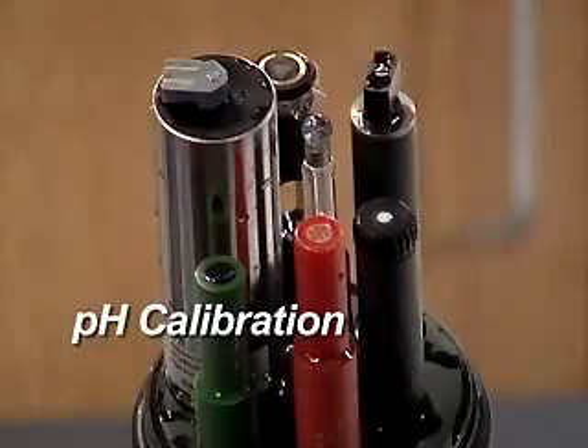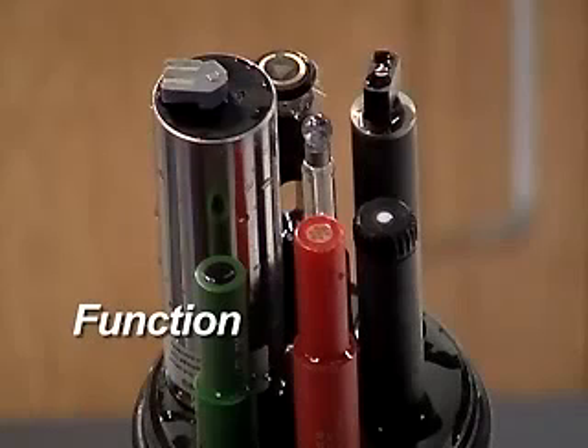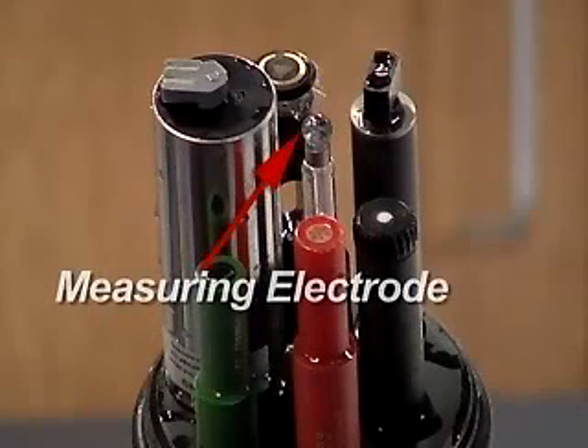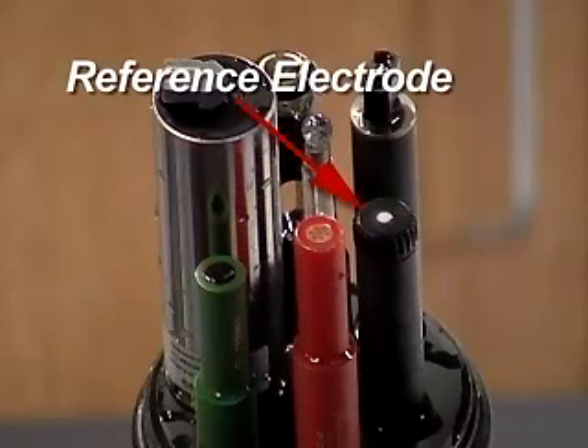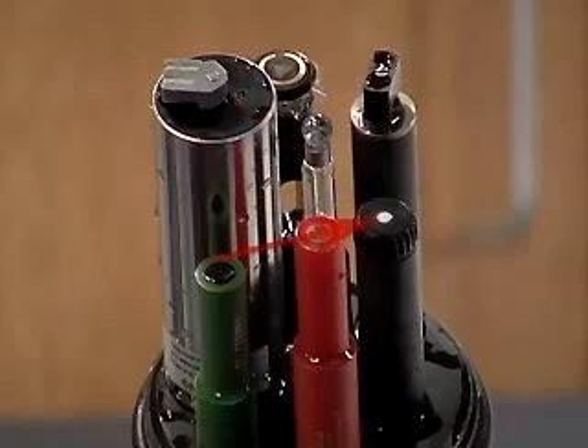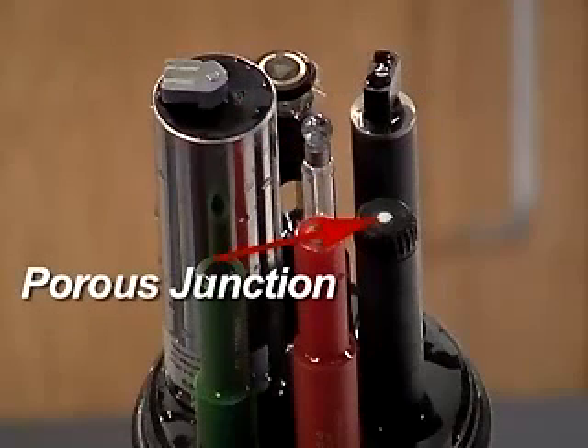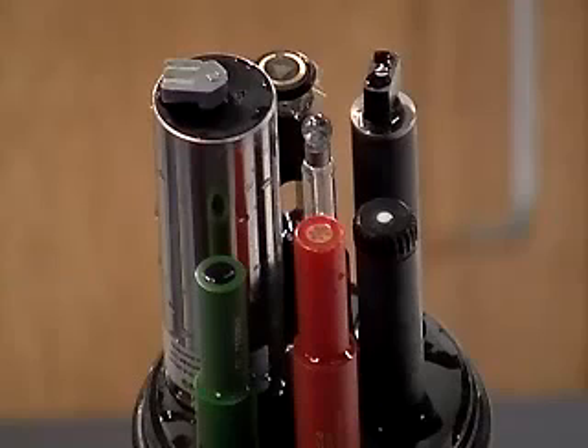pH calibration. Function. The pH sensor consists of two electrodes. The measuring electrode is surrounded by a glass bulb. The reference electrode is surrounded by an electrolyte solution and is separated from the water sample by a porous junction. By measuring the electrical potential between these two electrodes, the sensor can determine the hydrogen ion activity and calculate the pH for a given water sample.